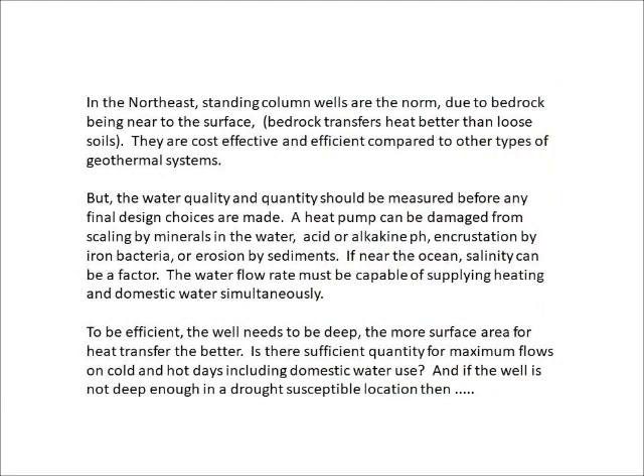In the Northeast, standing column wells are the norm due to bedrock being near to the surface. Bedrock transfers heat better than loose soils. They're cost-effective and efficient compared to other types of geothermal systems, but the water quality and quantity should be measured before any final design choices are made. The heat pump can be damaged from scaling by minerals in the water, acid or alkaline pH, incrustation by iron bacteria, or erosion by sediments. If near the ocean, salinity can be a factor.